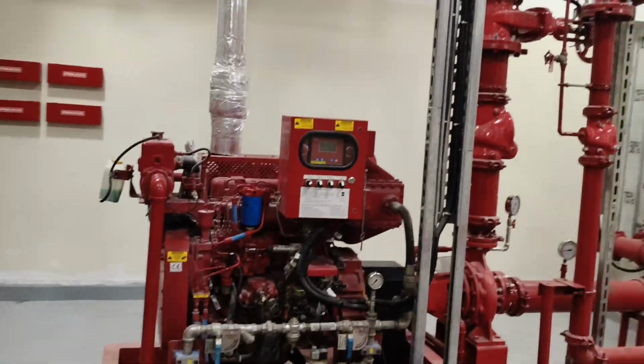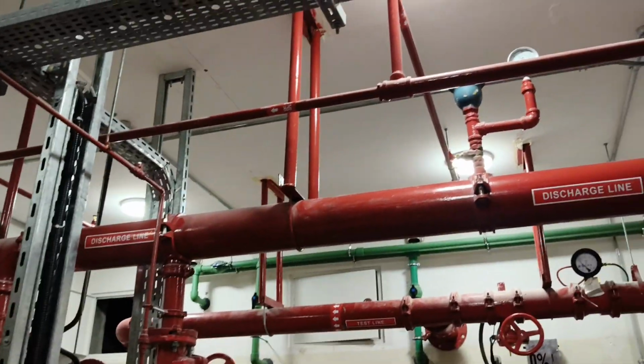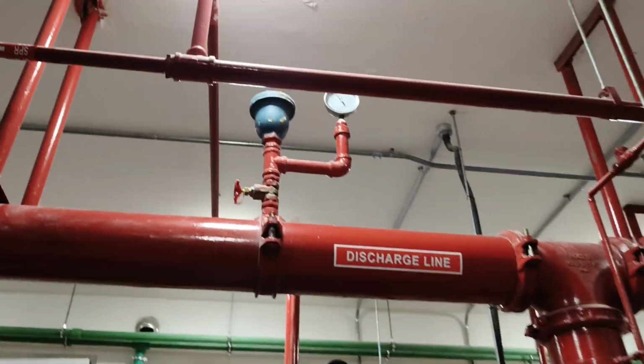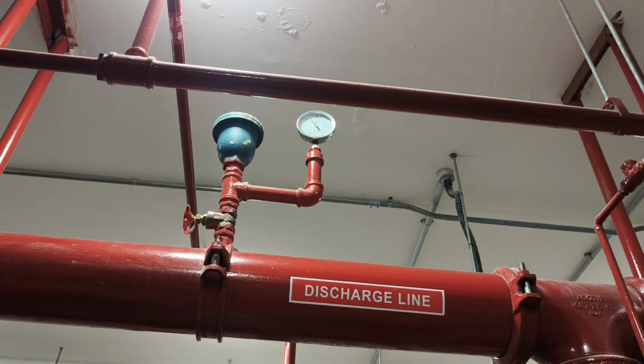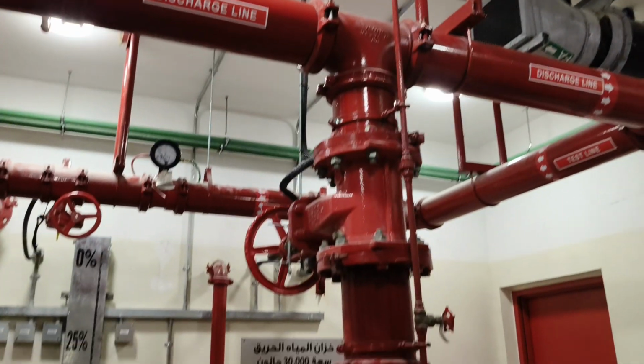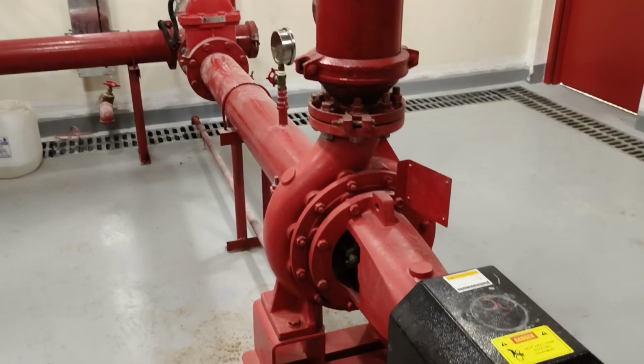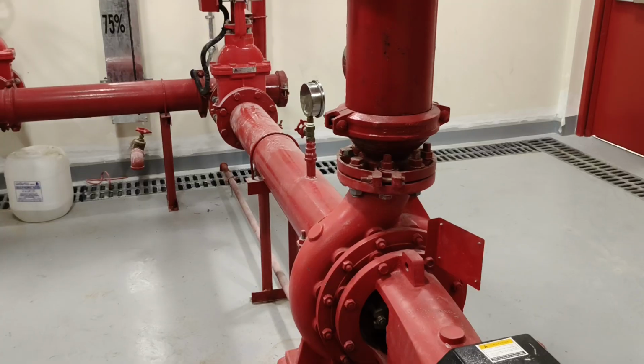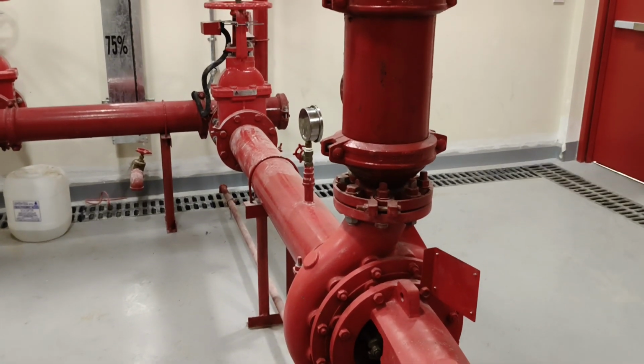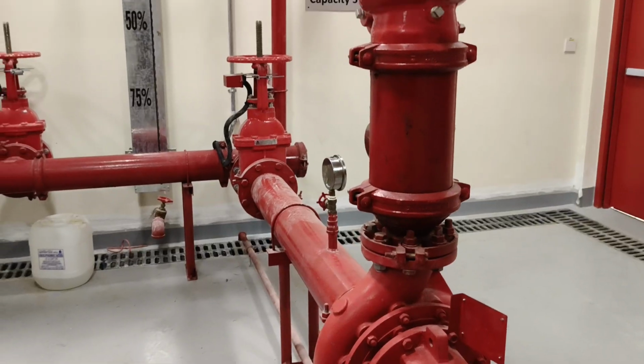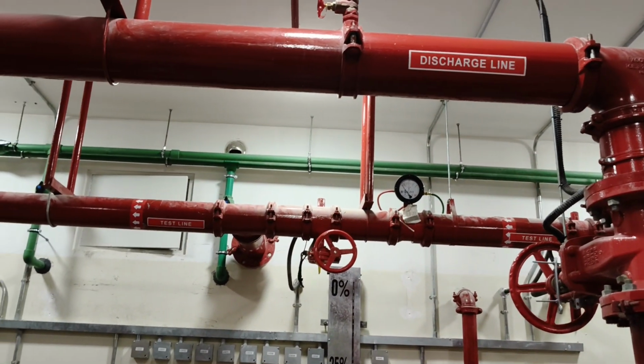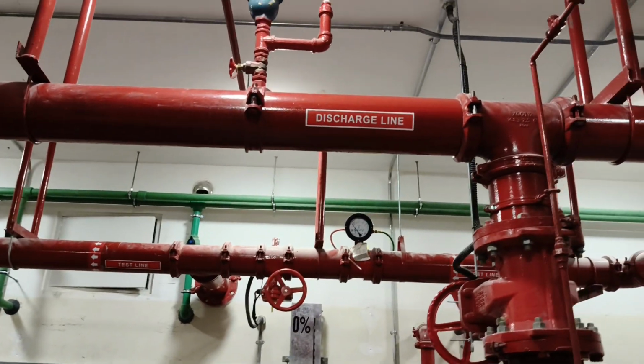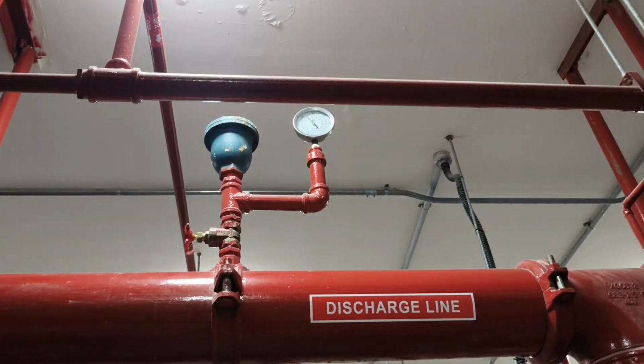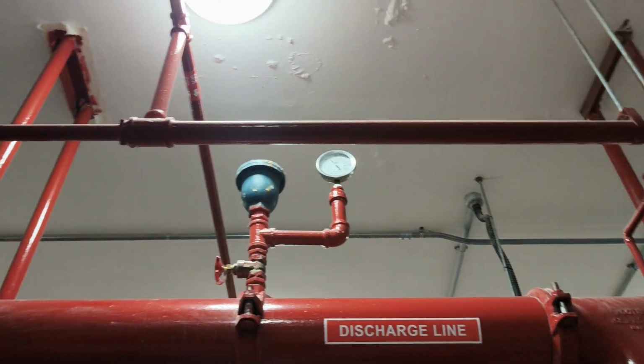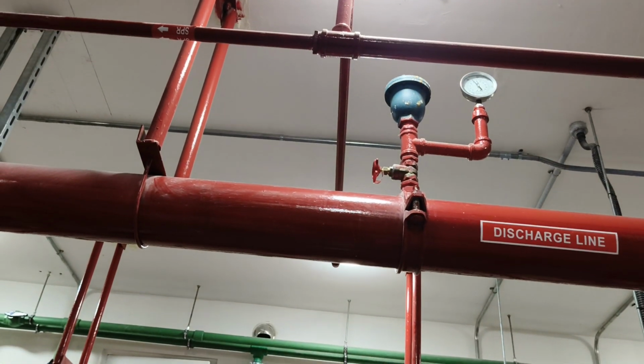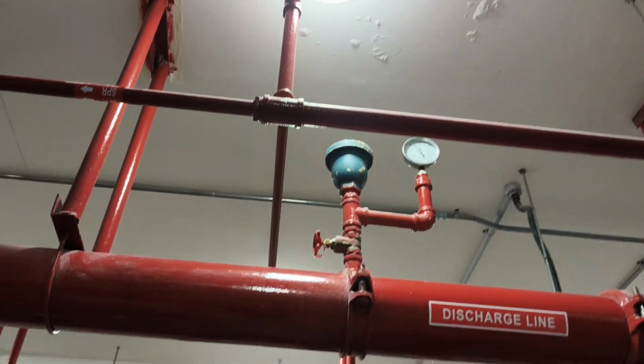so the diesel is just the same. You can see the main discharge header has an air release valve, and it also has a pressure gauge. All right, it is important because this is an end suction pump. It's not like the horizontal split case, where you can put the air release on top of it, right? So to eliminate the presence of air, that is why we are putting the air release there, so any air that is trapped in the lines can be released by the air release.